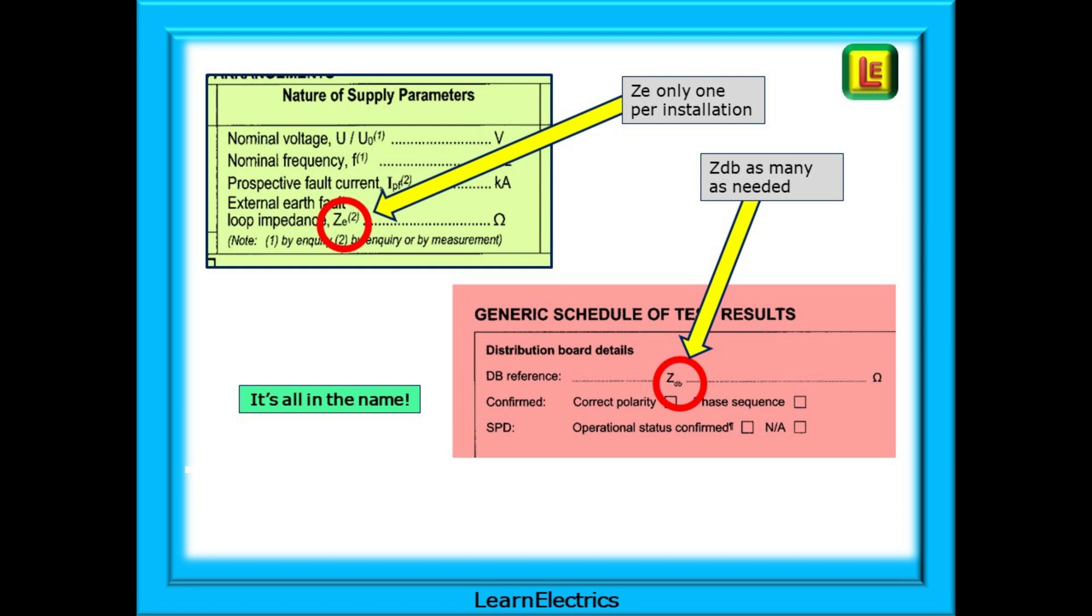ZDB just means the earth fault loop impedance measured at the main switch of this consumer unit. There is only one ZE for an installation, the point at which the supply enters the installation. But there can be as many ZDBs as needed. It's the same measurement, the same point on each consumer unit. It's just the name that we call it that has changed. All that ZDB means is the Z or impedance measurement at this particular distribution board. ZDB.